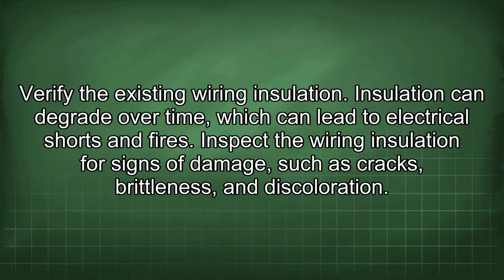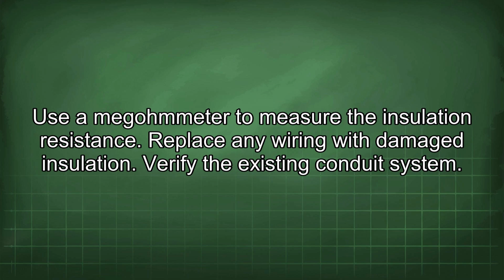Verify the existing wiring insulation. Insulation can degrade over time, which can lead to electrical shorts and fires. Inspect the wiring insulation for signs of damage such as cracks, brittleness, and discoloration. Use a megohmmeter to measure the insulation resistance. Replace any wiring with damaged insulation.